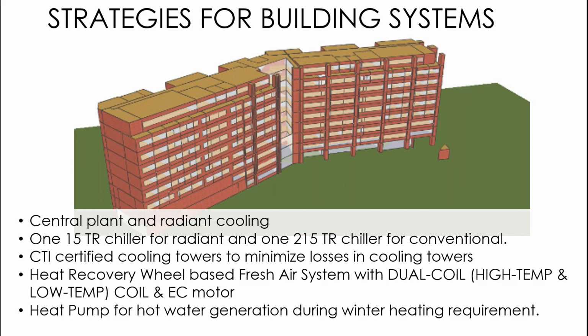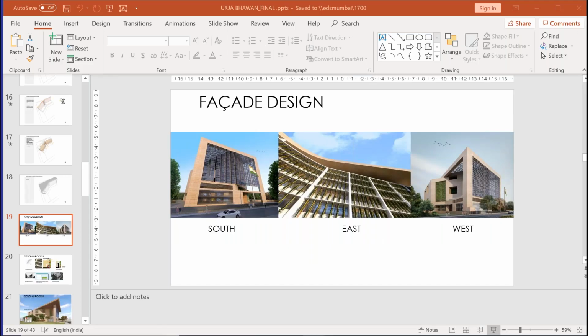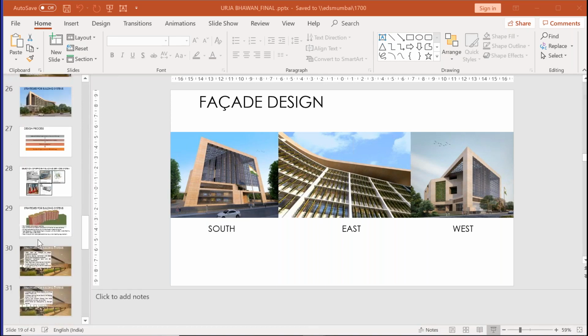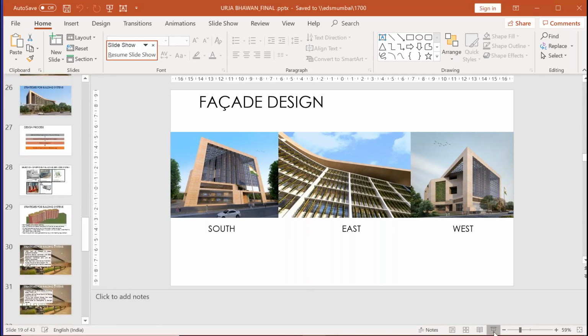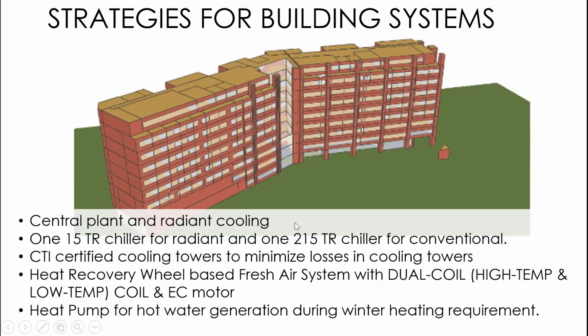In places like Mumbai and Chennai, the loads are high because of latent load. But in Delhi, loads are high because of sensible load. Now, when we design radiant, radiant can only take care of sensible load. The humidity load and the fresh air always have to be provided through the air handling unit. So what you see here is a hybrid system, with a conventional chiller and a radiant chiller. The conventional chiller takes care of the latent load and the fresh air load, and the radiant chiller takes care of almost 70 to 80% of the sensible load through baffles.